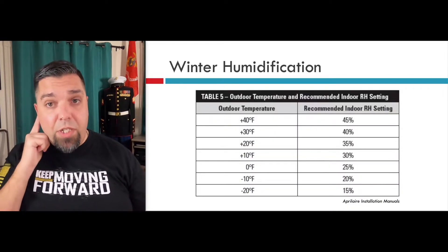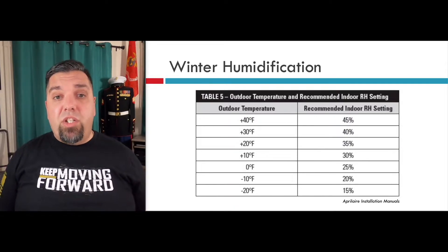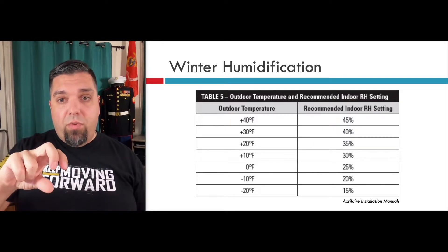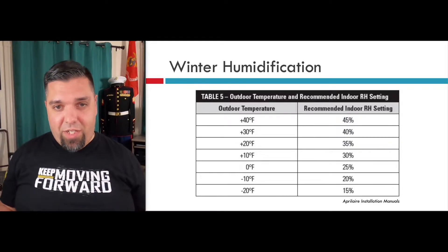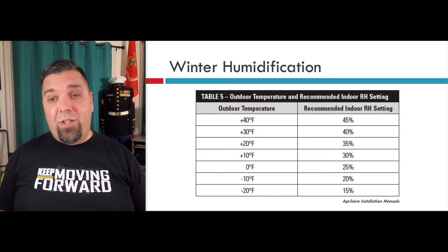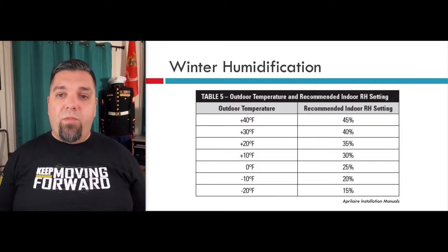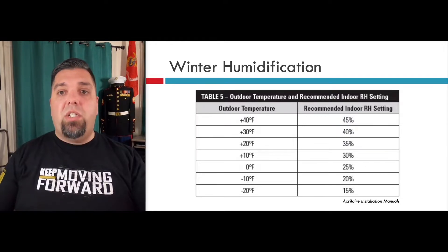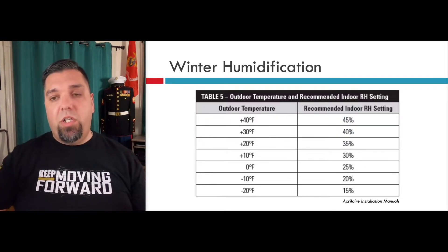You can see here: outdoor temperature and recommended indoor settings. This is right out of the Aprilaire installation manual. Unfortunately, a lot of people are not going downstairs and adjusting their relative humidity setting based on the outdoor temperature, because the outdoor temperature changes every day — it can change drastically in New England. If it's zero degrees outside, you want about 25 percent relative humidity. If it's warmer out, there's more moisture in the air, so you humidify more inside — the relative humidity setting goes up.